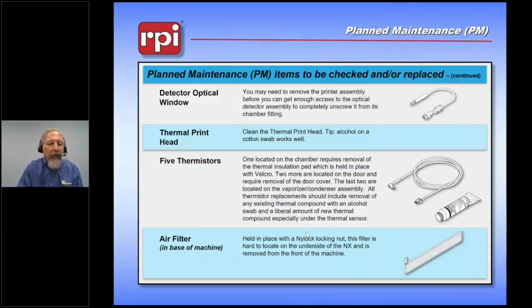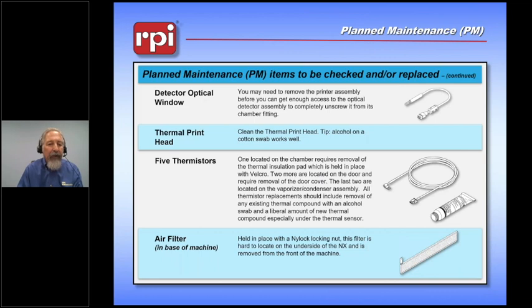As I mentioned earlier, there is also a third window, part of the detector optical system. If you need to get to that third window, if you want to polish it or clean it, be very careful again when removing the optical detector. It is extremely static sensitive. Make sure you do not remove that cable with the machine plugged in, and make sure that you are wearing proper static safe wrist straps to make sure that you don't damage the optical detector.